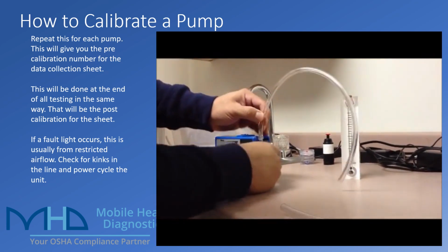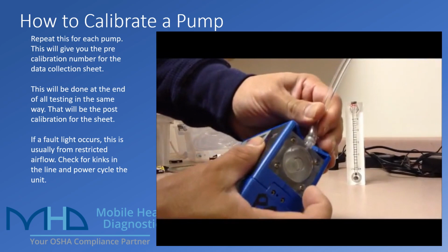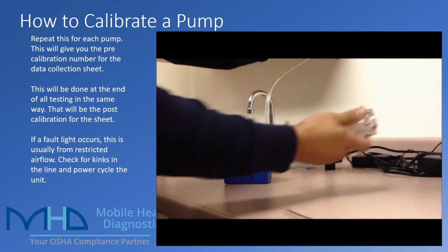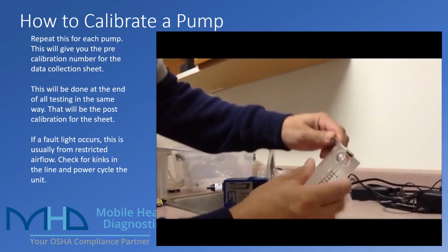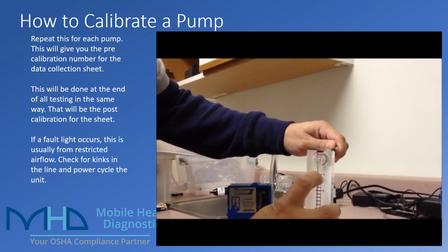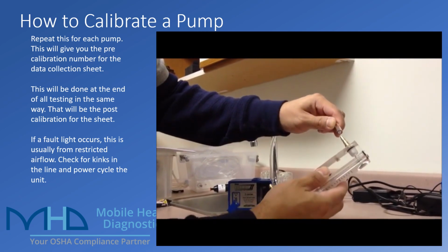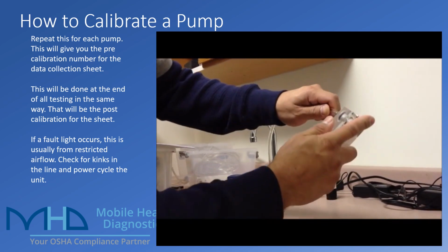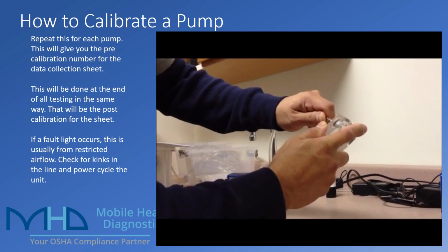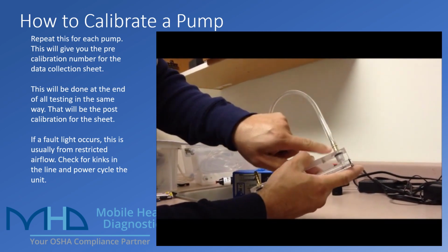anything beyond extra pressure. So from here, we turn on the pump and you can see that small little ball bearing that raised up there. That is what we are calibrating against. The way that you're going to read that is the centerline equator of that ball bearing. I think what's good to note here is if you can see the small ball bearing of the actual pump itself, it's showing quite a different value than what's actually on the calibrator.